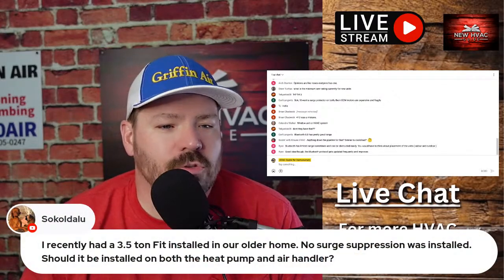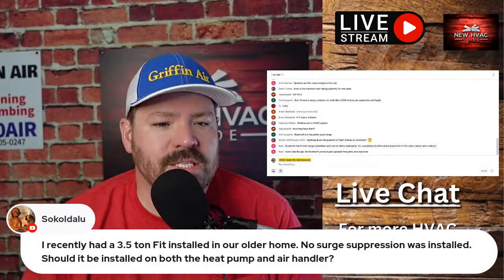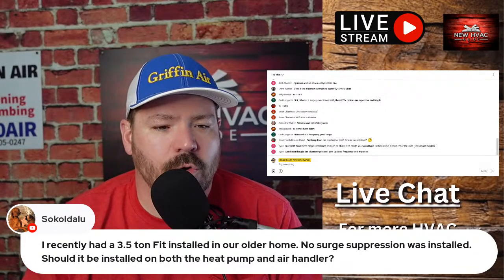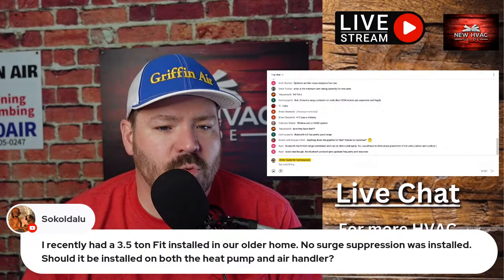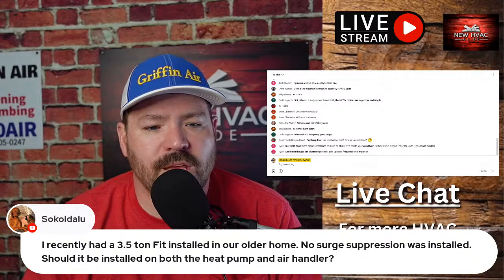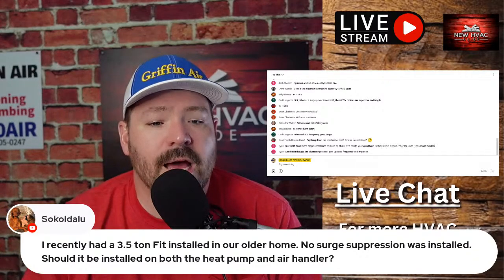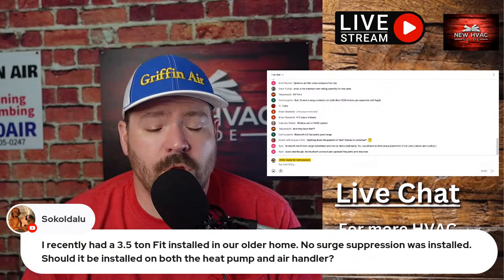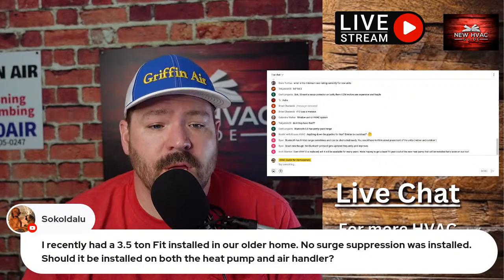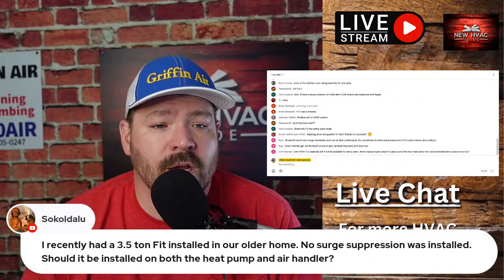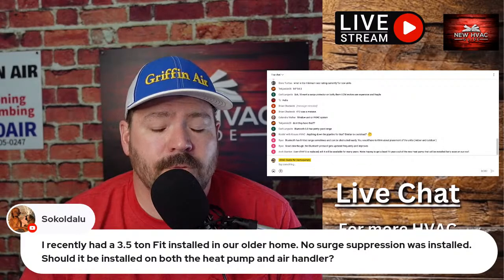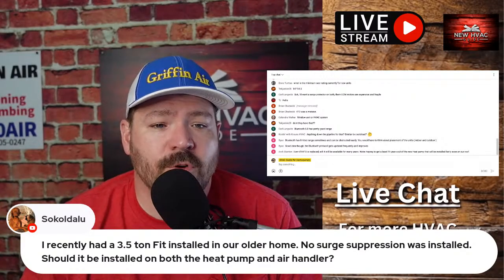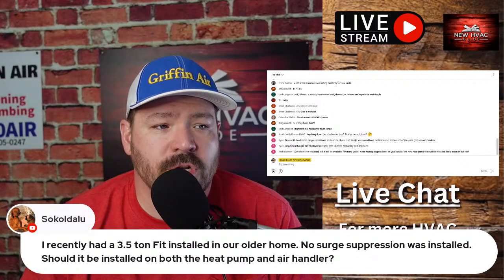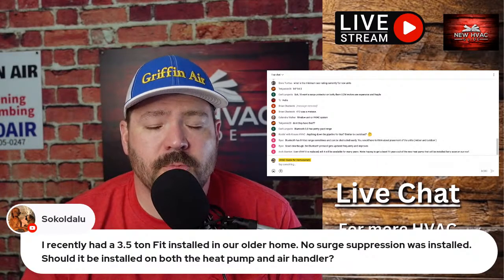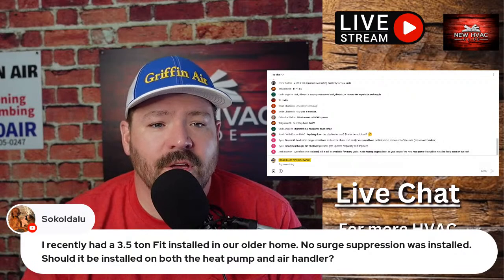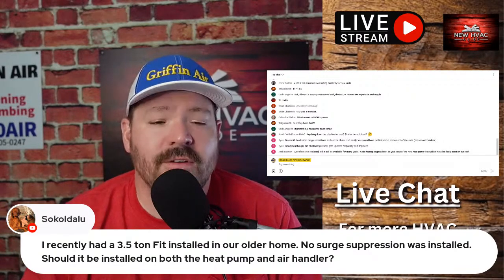Coldaloo says, I recently had a 3.5 ton fit installed in our older home, no surge suppression was installed. Should it be installed on both the heat pump and/or air handler? I definitely would have it installed on the heat pump, no ifs, ands, or buts. It's an inverter system, I would definitely have it installed there. The failure rate on those inverter compressors is significantly lower, especially if you have a surge protector on there. So definitely get that put on.